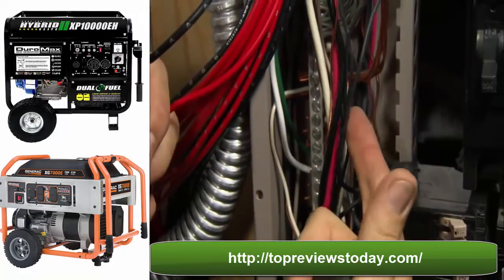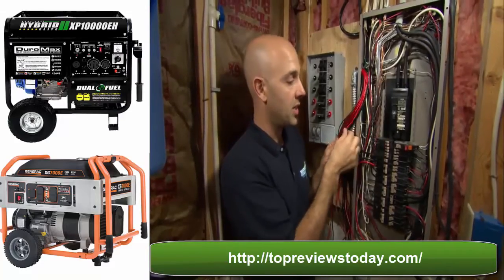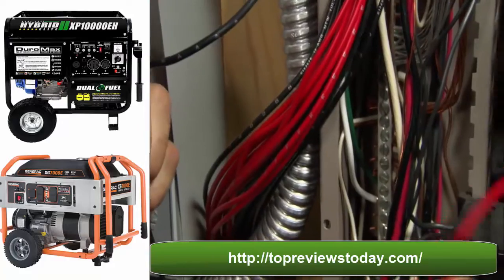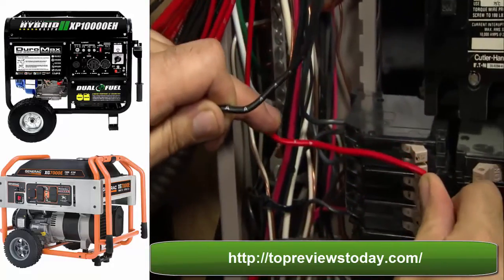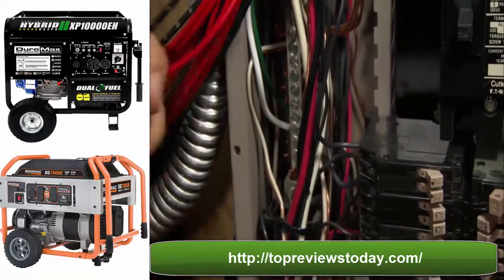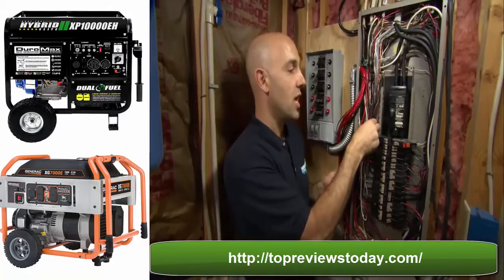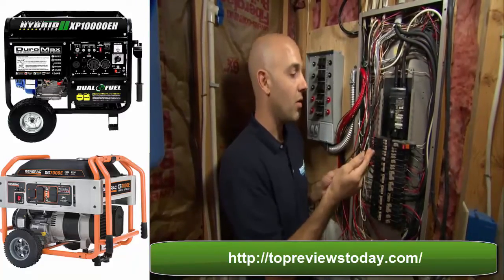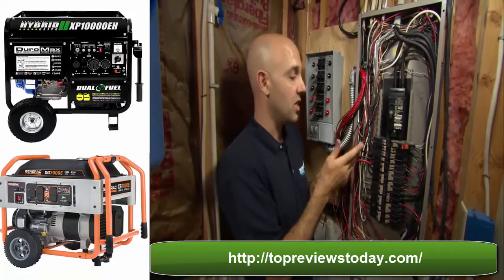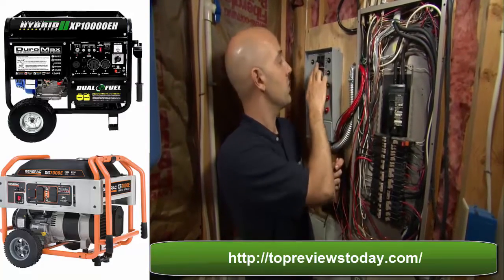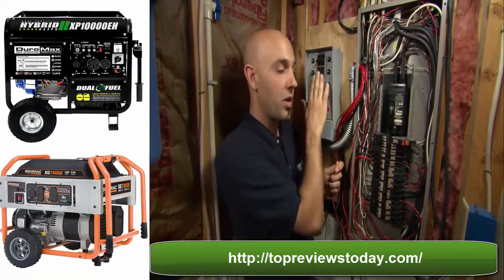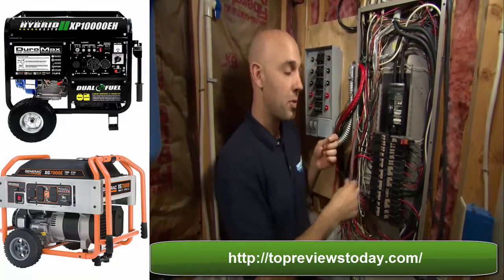We need to remove the branch circuit wire going up to the kitchen lights. We tie the red wire into the circuit breaker, and then we splice the wire going up to the lights with the wire from the transfer switch, and that allows us to have utility power during normal operation. In the event of an outage, we would switch this switch over to generator, and that would send power up the black wire to the kitchen lights.